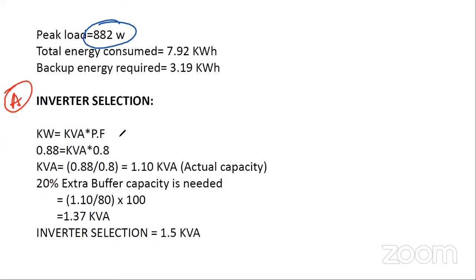So to arrive at the kVA, we just need to divide the watts by the power factor. We're taking 0.8 as the standard worst-case scenario. If you calculate, it comes to around 1.1 kVA. This is the actual capacity the inverter is supposed to be designed for.